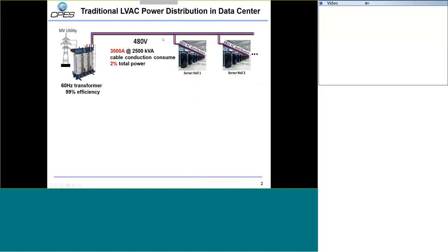One problem is that the power demand for data centers is becoming higher and higher. You can imagine the current on this distribution line is huge. For example, for a 2,500 kVA system, the current on this 480-volt distribution line would be more than 3,000 amps. This 3,000-amp current gives you huge conduction loss — the total conduction loss is around 2% of the total power.